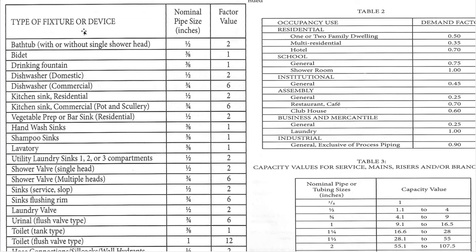Right here you have the fixtures or devices, their nominal pipe size in inches, and their coinciding factor values. So everything that's half-inch will be a factor value of two. Everything that's three-eighths will be a factor value of one, three-quarter is six.